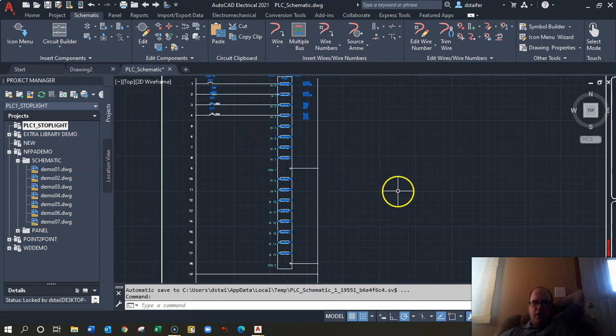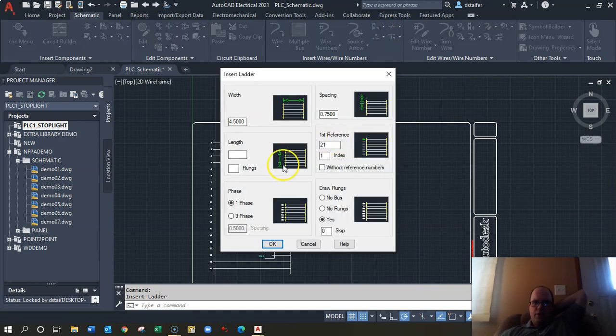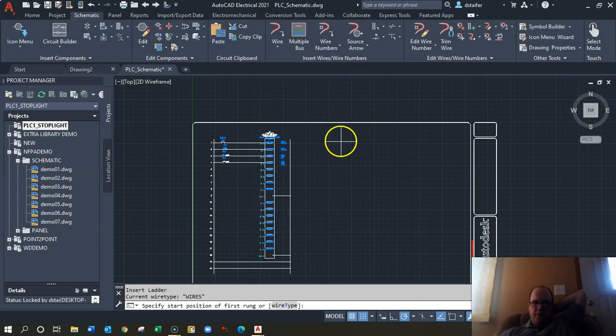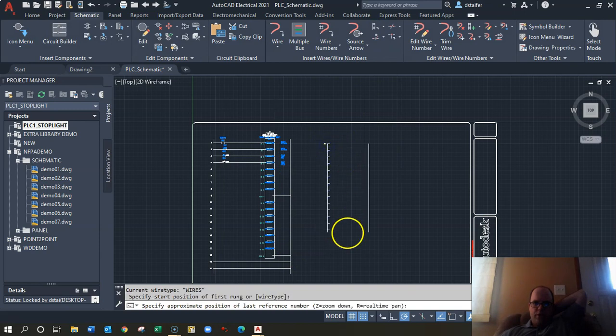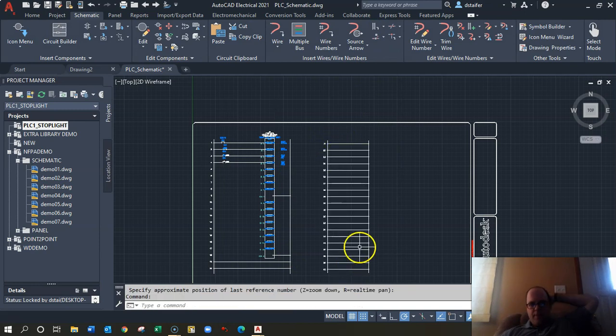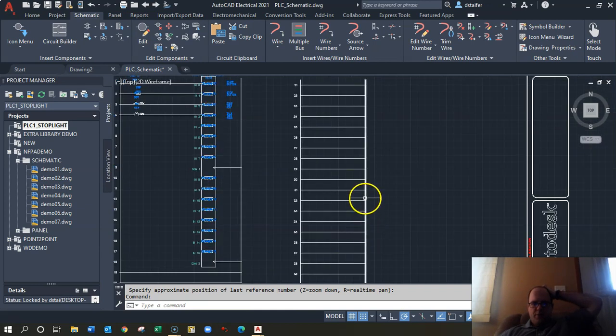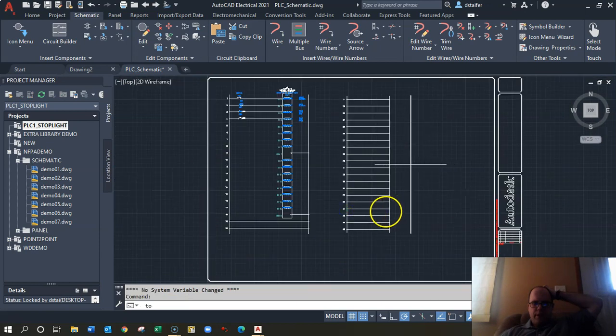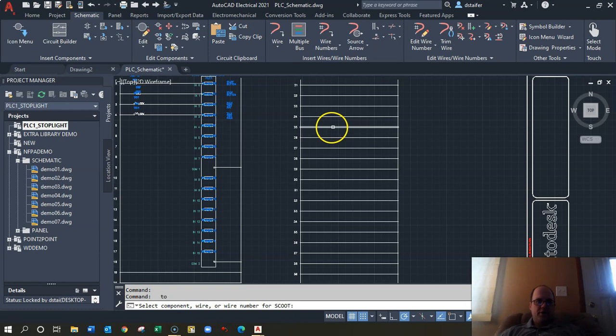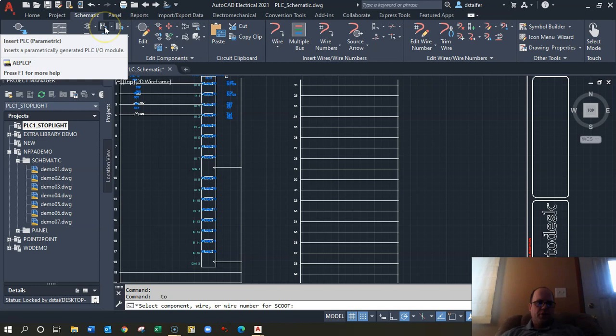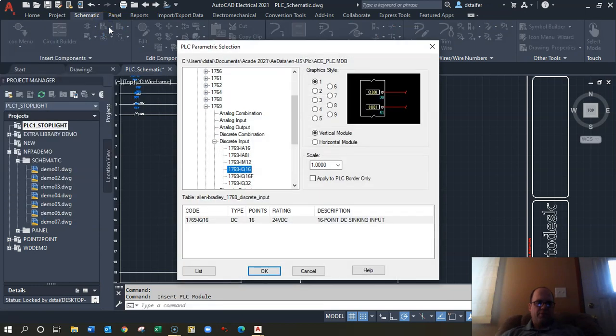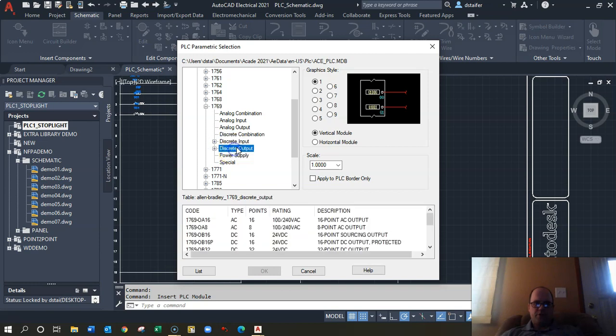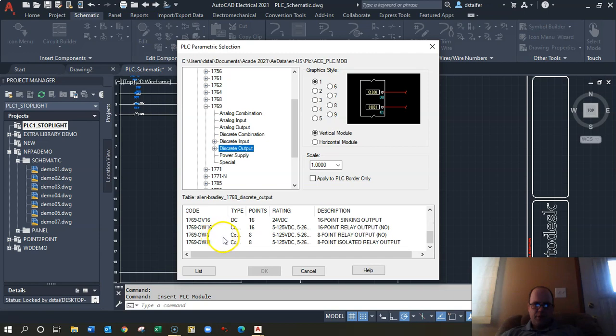Let's repeat the process for our output. Go to Insert Ladder, single phase, and draw a ladder on the other side. Right-click and hold and do Scoot to give yourself more room. Now go to Insert PLC Parametric and add an output card — a discrete output, 16-point DC in this case.